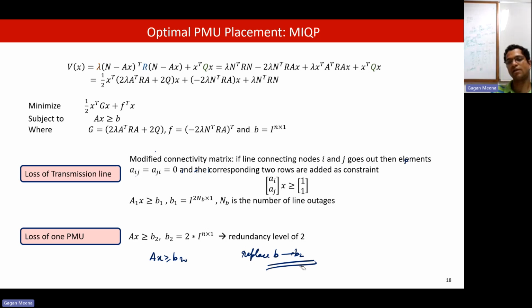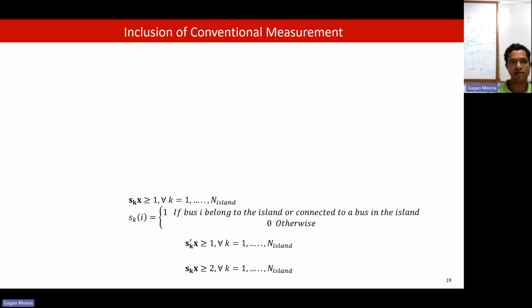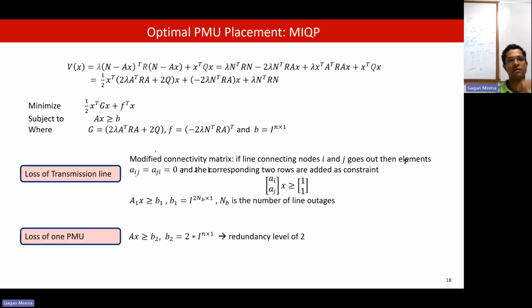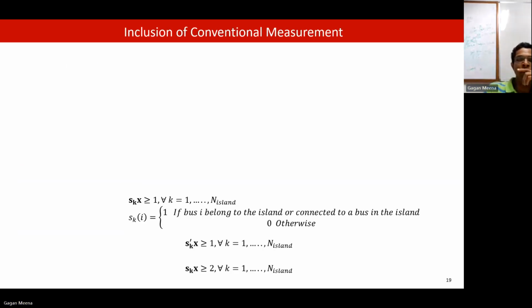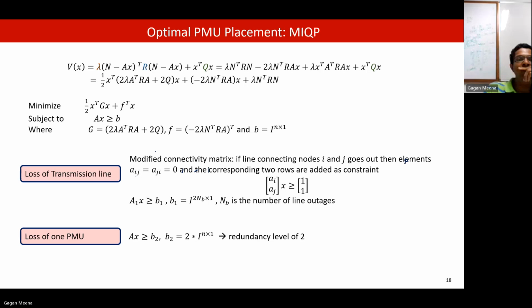So we are increasing the redundancy, the number of redundant PMUs, by 1 at each bus. That's how we ensure that if one PMU goes out, since we have a redundancy level, that will be covered. So that bus will be observed by 2 other buses.